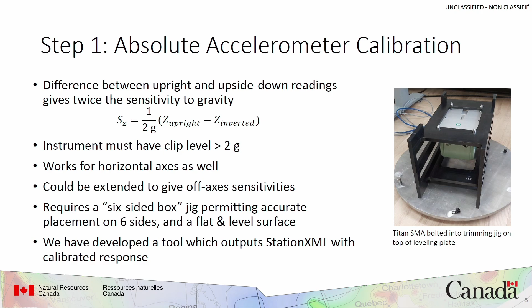The instrument has to have a clip level of at least 2 Gs, and we place the sensor on all 6 sides to get 3 sensitivities. The picture shows a leveling plate, which is not required if you have a flat, level surface. And the whole process takes a few seconds per side and a minute total.